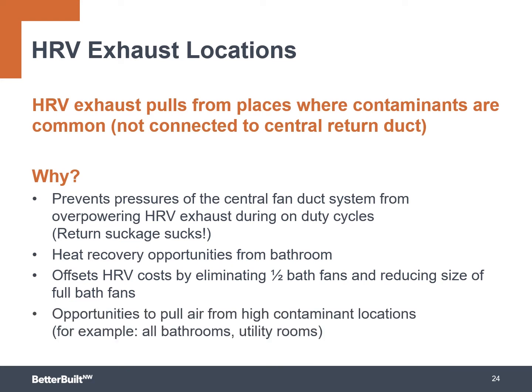And then, of course, opportunities to pull air from the high contaminant locations is always a good thing. All of the bathrooms, the utility rooms, the laundry rooms, those type of places, that's where we create pollutants on a very common level. Again, we're not really saying to do this with the kitchen. We know that at some levels of efficiency, when you get down to the passive house level, this becomes a much more common approach. But for most of you builders out there, don't do it out of the kitchen. Go ahead and do it out of all the bathrooms, utility rooms, laundry rooms.